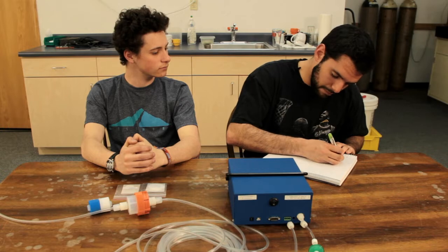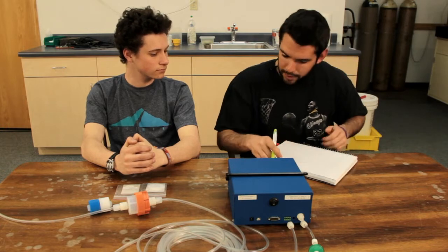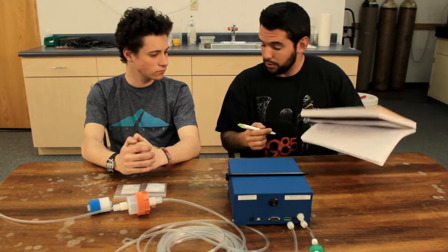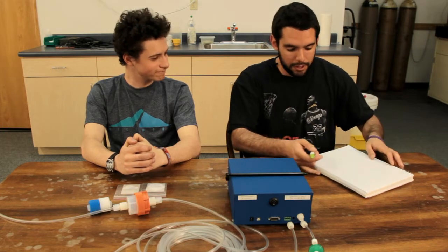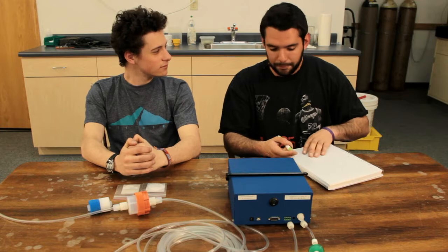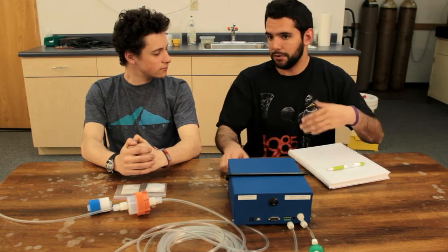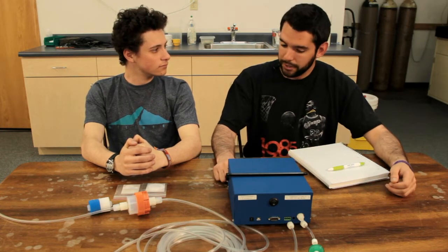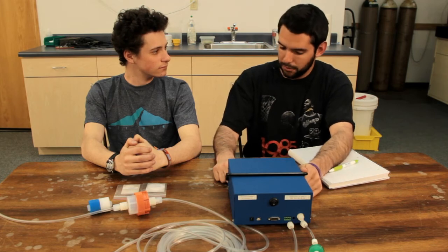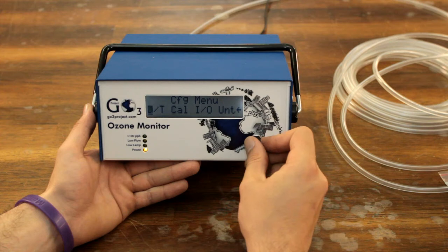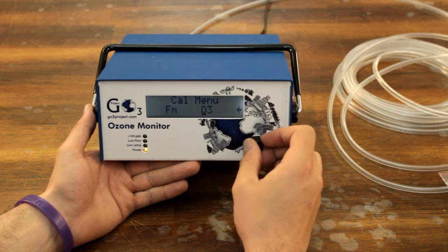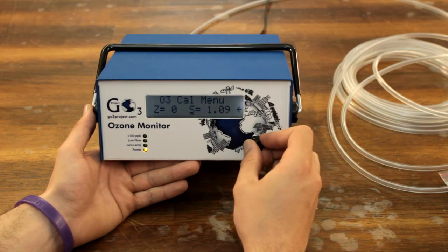So I'm doing my measurements, and once I've got them, I'm going to turn those over to Scout. She's going to throw them into an Excel sheet and get an average for us. So Scout got an average of -2. The way that we're going to account for this is we're going to go back into that same menu where we changed the Z. So Menu, CFG, Cal, and change that Z to 2, the direct opposite of what we got, -2.